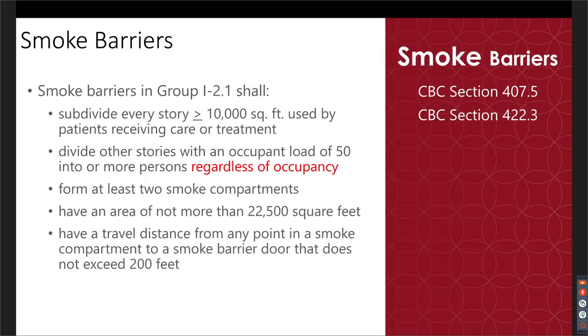So smoke barriers. We talked earlier about smoke compartment requirements in the I-2 ones, the sections 407.5 and then 422.3. So the 407, of course, is for your I-2s, 422 for your ambulatory care facilities.